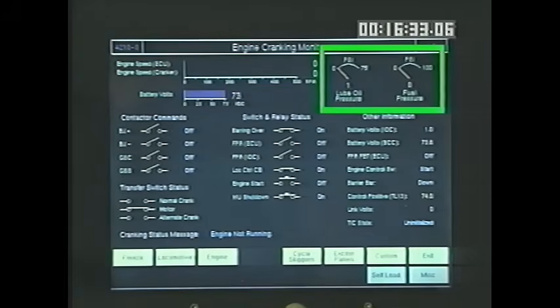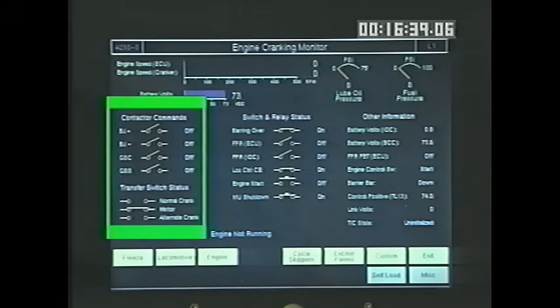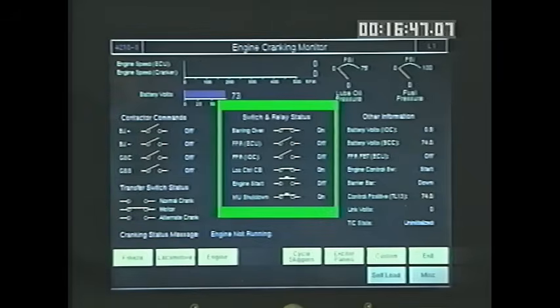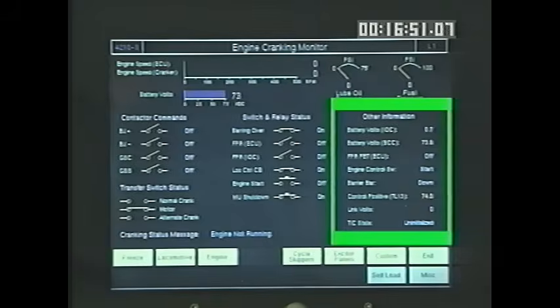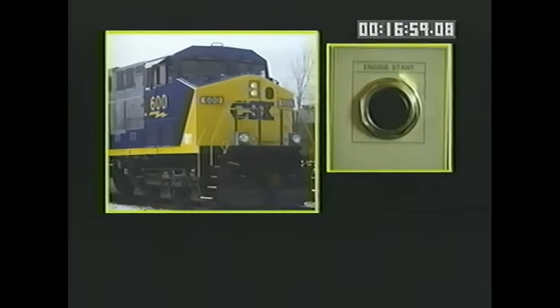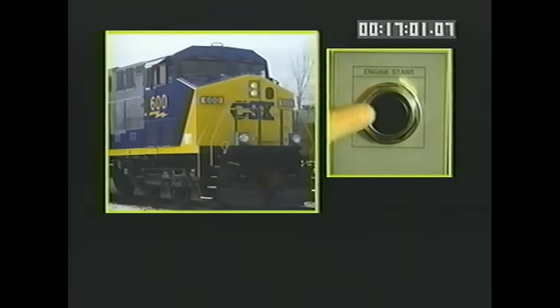Lube oil pressure and fuel pressure are displayed at the top right area of the screen. The left column in the center of the screen depicts the contactor's commands and transfer switch status. The center column gives switch and relay status. The right column displays other information related to engine control. The automatic starting process is just one of many computer-controlled operations on the AC6000.